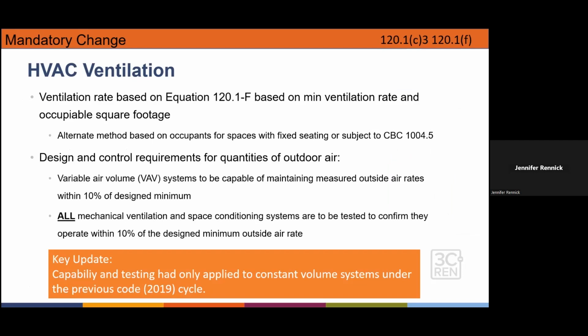On the ventilation side for HVAC ventilation, basically, there hasn't been a lot of changes other than now saying that the equipment has to have better diagnostic capabilities for showing that the equipment is going to meet the 10% design, kind of within 10% design of outside air, that used to only be applicable to constant volume single zone systems, but now it's applied across the board to variable air volume systems as well. So this stuff, as architects, you may not see any difference, but the mechanical engineers are going to need to be aware of it.